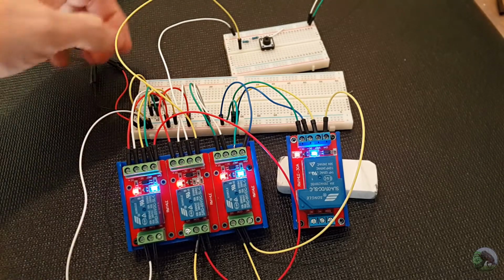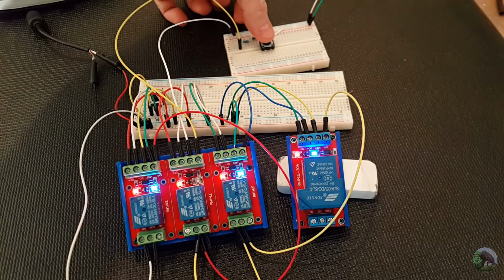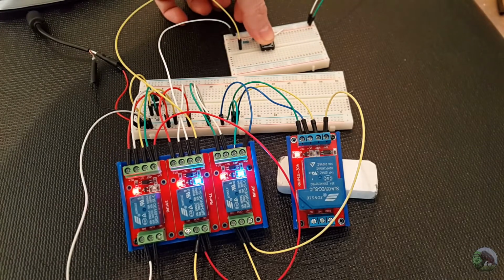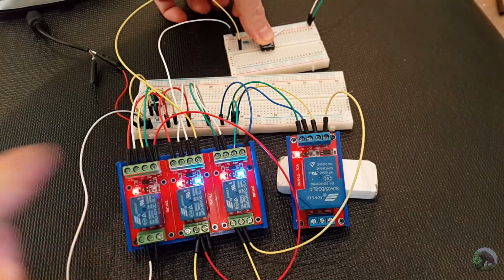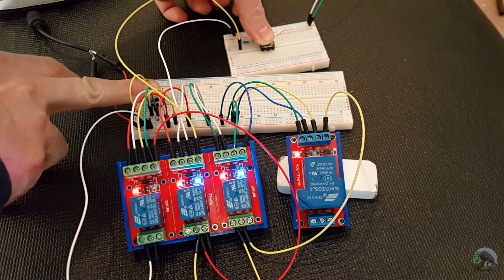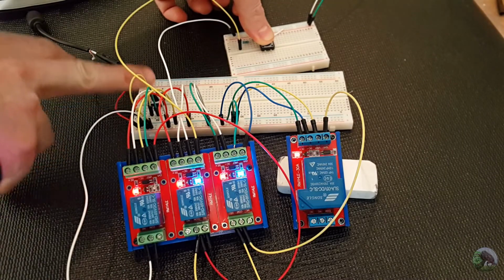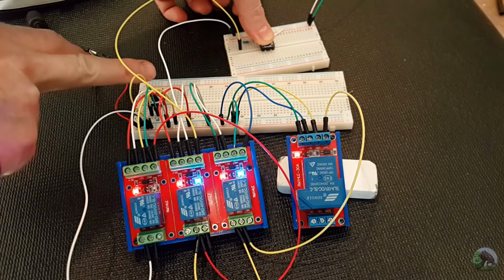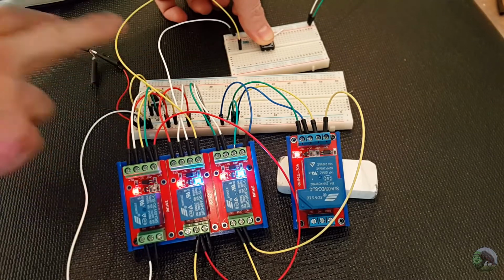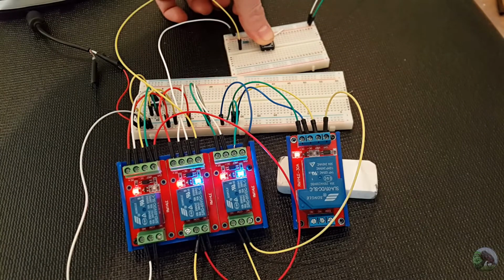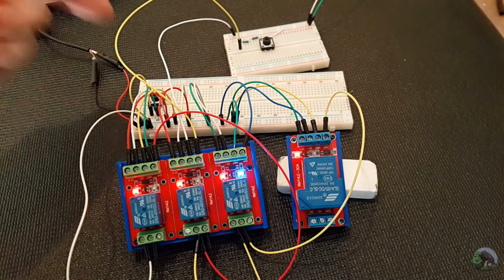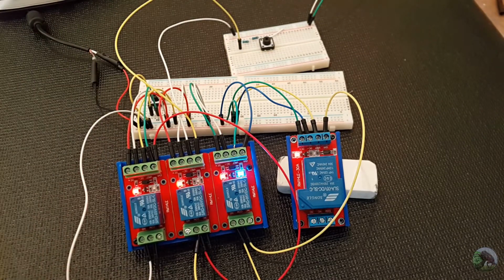And something good to note here is if a smoke detection signal comes, but it's not intermittent or it's still occurring when a human comes to press this button, you'll see that it's now not latching. It's now intermittent. And the moment you let go of that button, all of the relays go off. So it's kind of important to know that that's the behavior of the circuit.